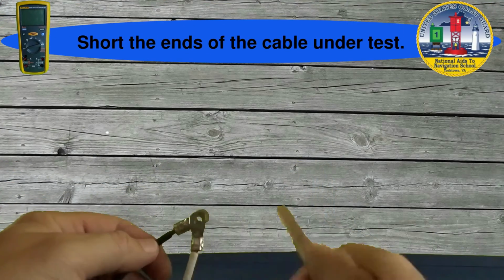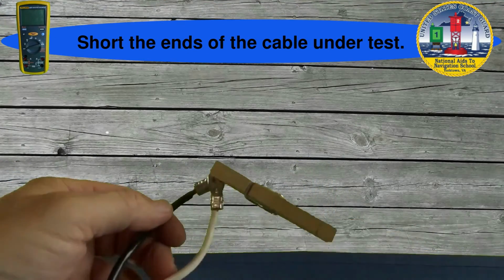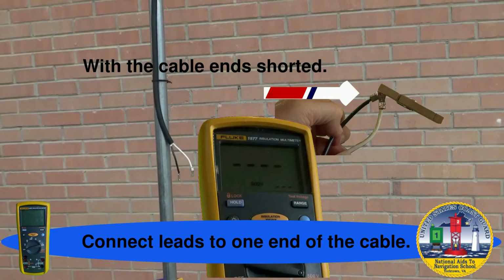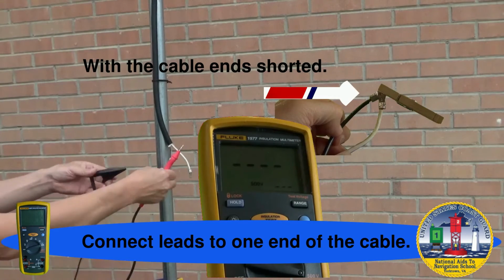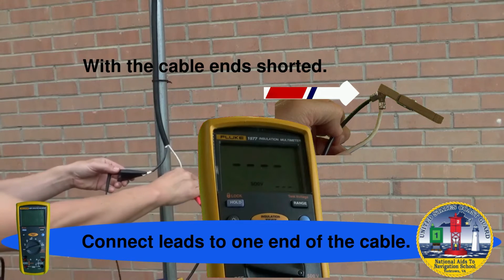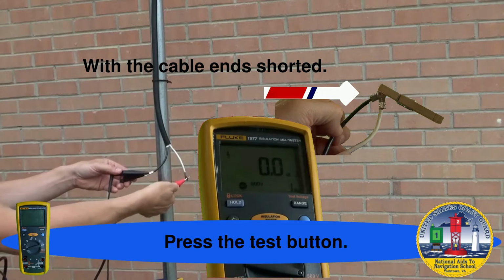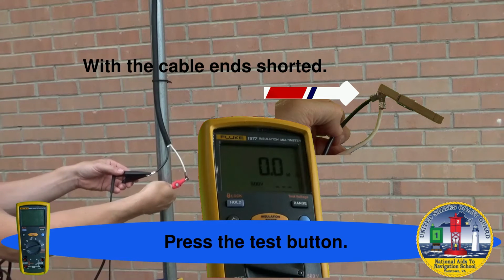Disconnect your test equipment and short the opposite end of the cable under test. Again, connect your test leads and press the test button. The meter should read no resistance. Note in your servicing guide that the reading is only required to be less than 1 megaohm.